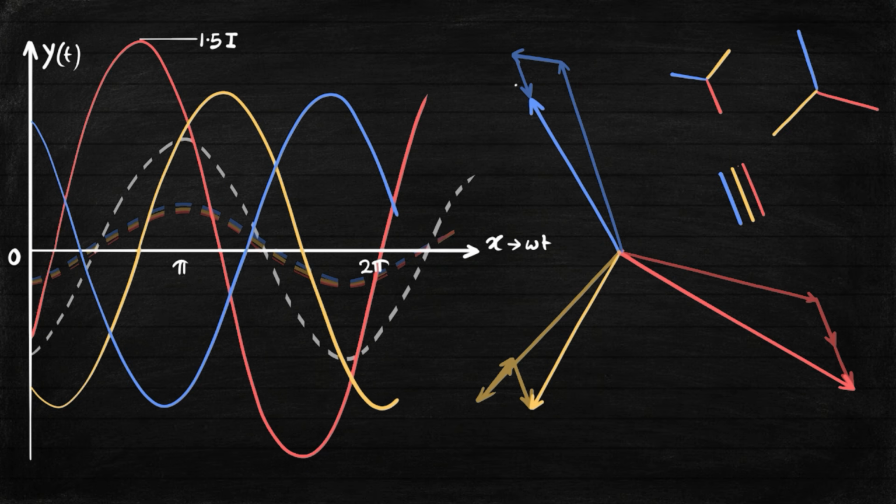When a fault occurs in the system, the three-phase system can contain three types of symmetrical components. One is the set of positive sequence currents. These currents continue with forward phase sequence and contribute to the operation of the system during the fault. The second one is the set of negative sequence currents. This set of currents has a reverse phase sequence and can produce a reverse rotating magnetic field.